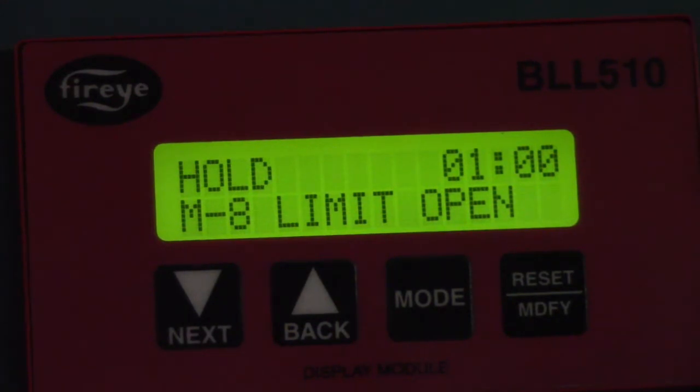This video will help me troubleshoot and find the problem that's preventing this boiler from going into purge. The main indication by the FireEye is that we are in M8 limit open. We need to find out what that means. It's not telling me specifically what's holding the boiler out, but it is giving me a clue: M8.